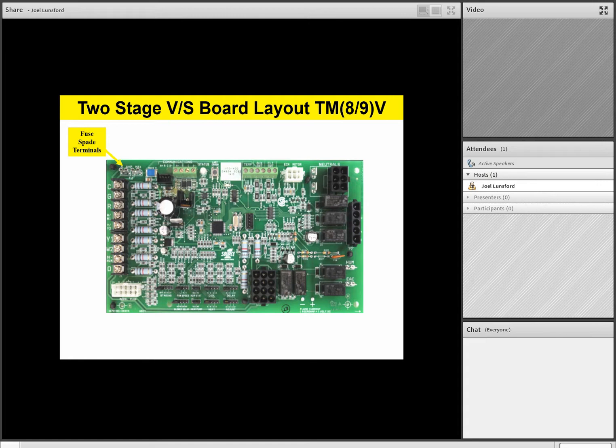As we move around the board, we see we have some communication screw terminals. This board is communicating capable with a 4-wire communicating system. If you look closely in the photo, you'll see there's A, B, C, and R terminals, and those are our communicating terminals. Right next to the communicating screw terminals, we have a status LED, and again, it's a 3-color or tricolor LED. It'll flash either yellow, also called amber in the workbook, red, or green based on the fault that's being detected.